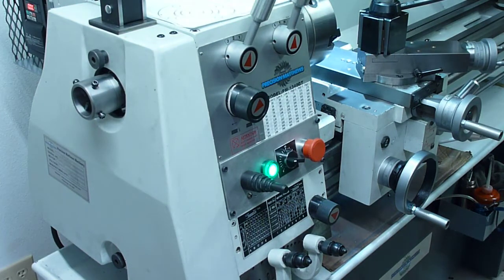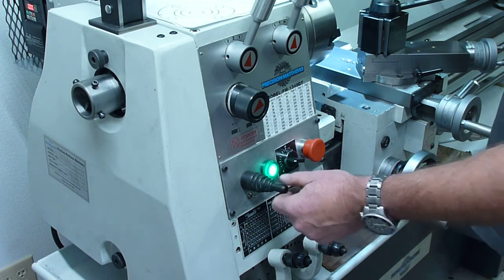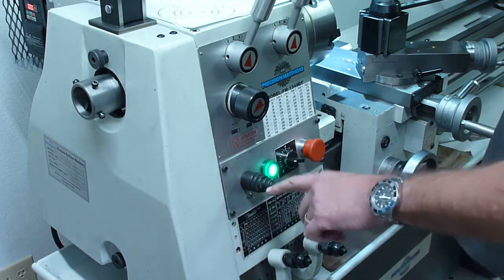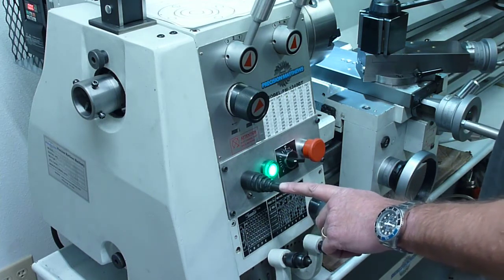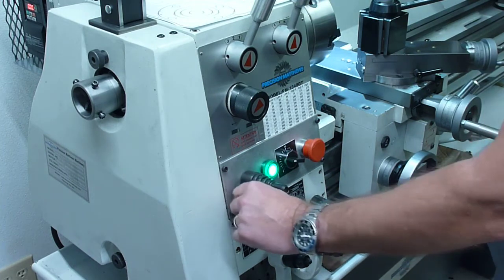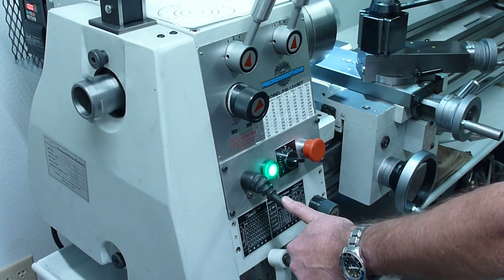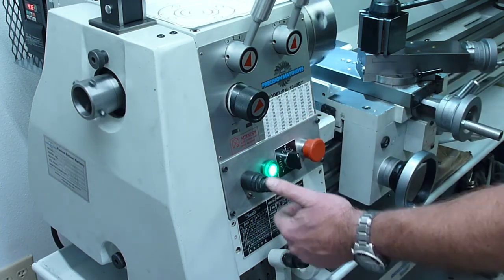I set the jog feature up such that I can jog in forward or reverse and I can jog at two frequencies. The first frequency is a frequency range that's preset within the VFD from five to ten Hertz. So moving the switch to the left position in this instance, I can jog at jog frequency.